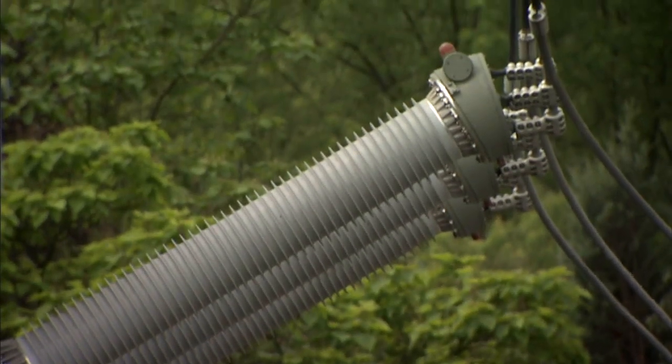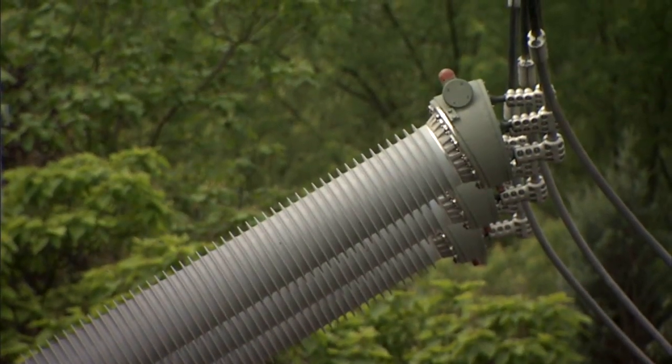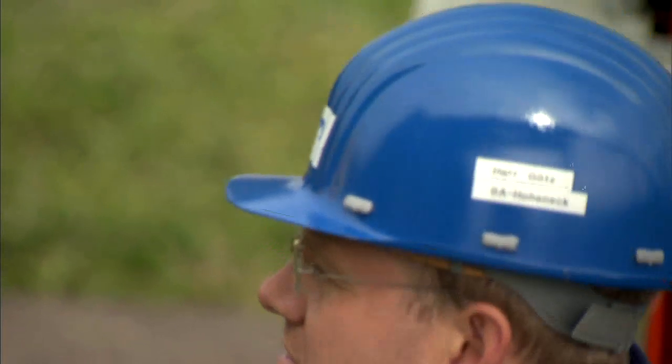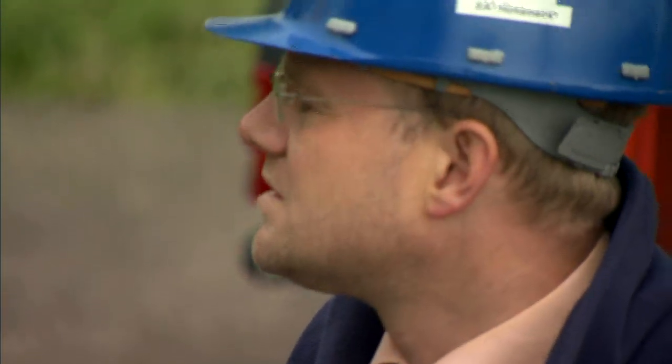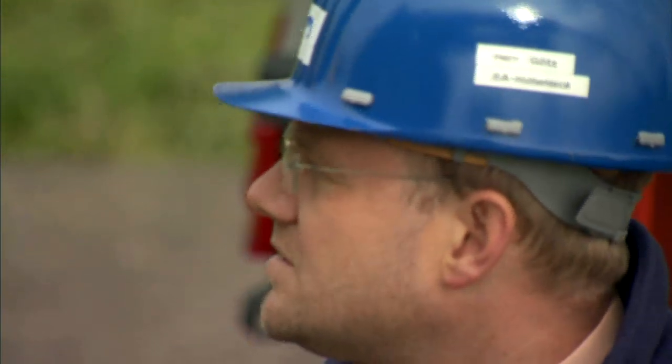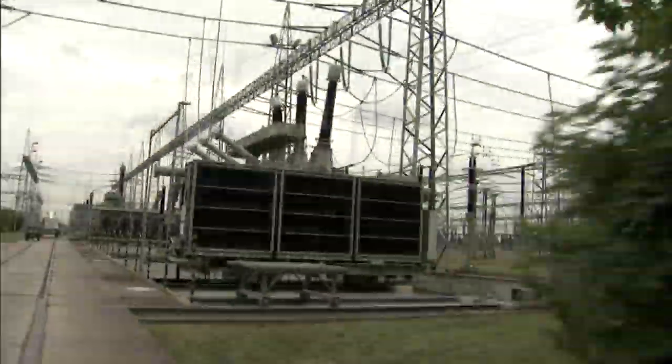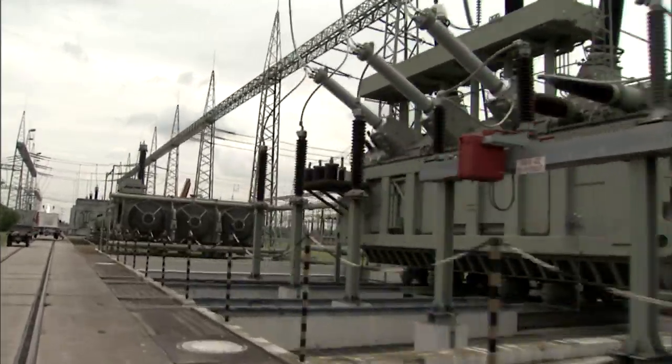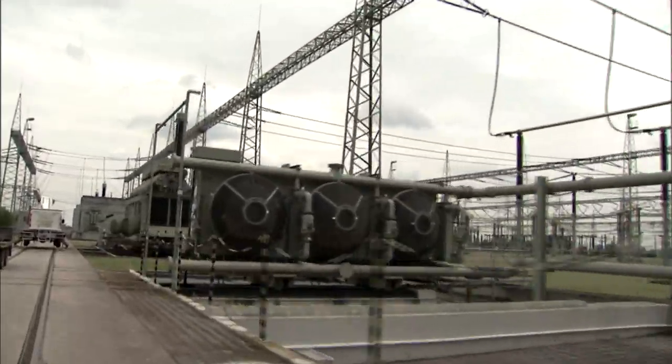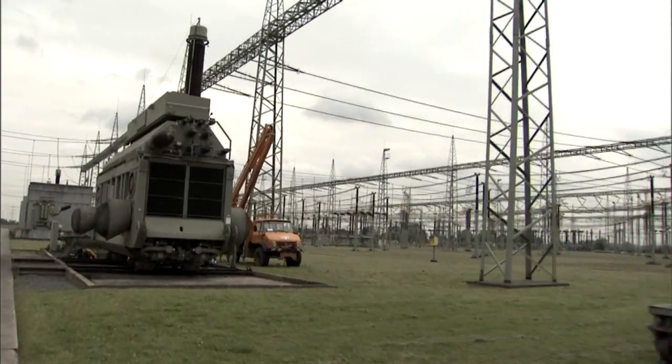Utilities have moved from time-based to condition-based maintenance, with routine checks taking place less frequently. This increases the demand for testing to fit the needs of asset managers and engineers to run their transformer fleets at the lowest cost without decreasing the security of the power supply.